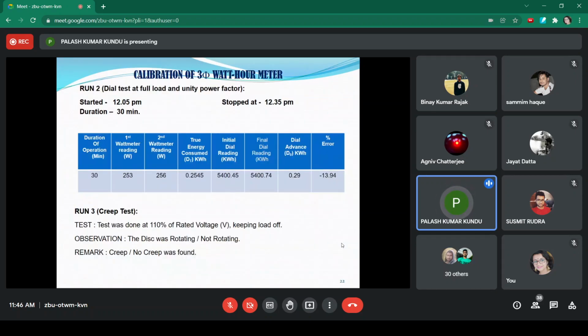Then for the long duration dial test over 30 minutes, that is half an hour, the standard wattmeter readings are summed, and the true energy consumed in kilowatt hours is calculated by summing these two readings over 30 minutes. The initial and final readings are taken from the test energy meter, and the difference is 0.29. It is higher than the true energy consumption over the 30 minutes in kilowatt hours, and the error becomes negative in our case. So that is the interpretation of the sample reading.